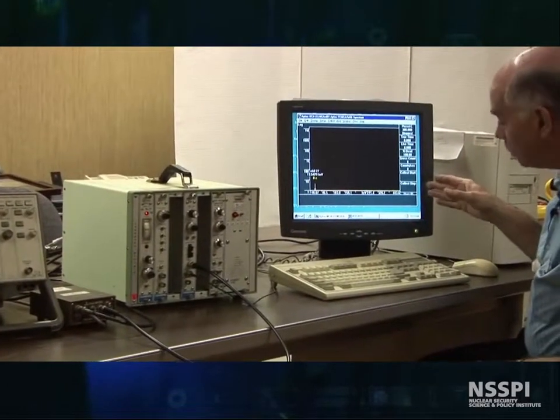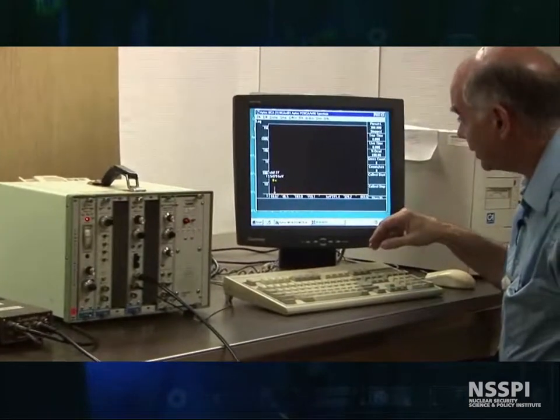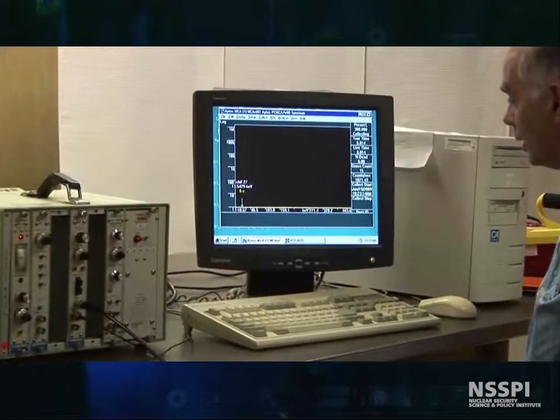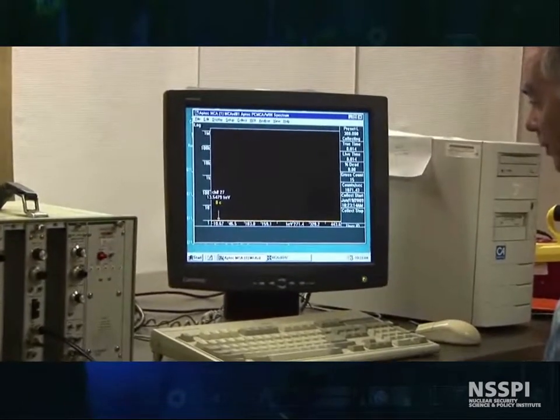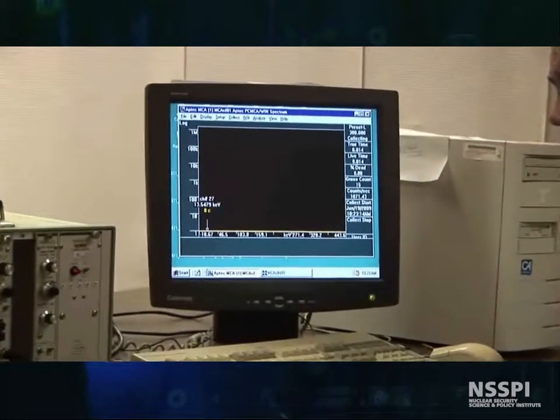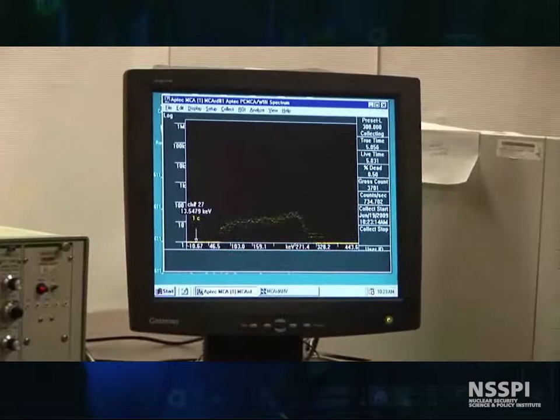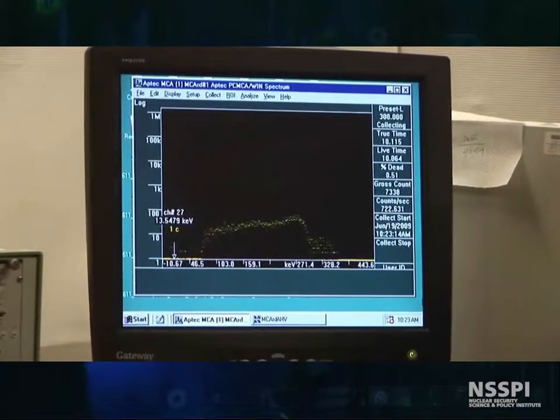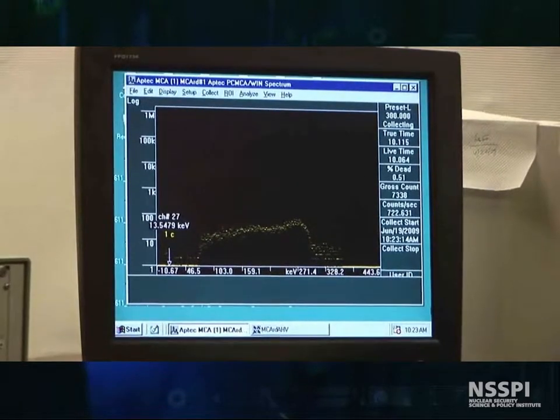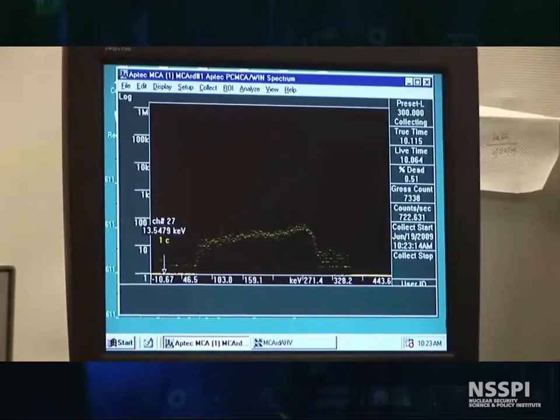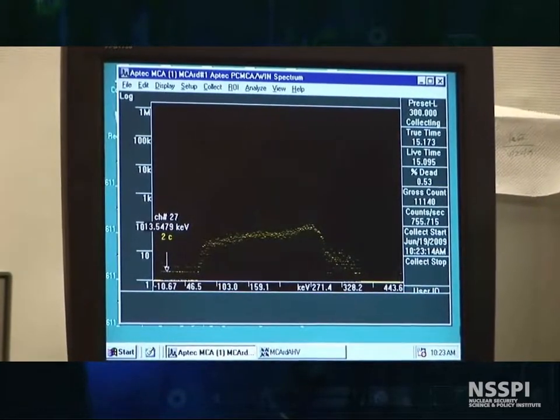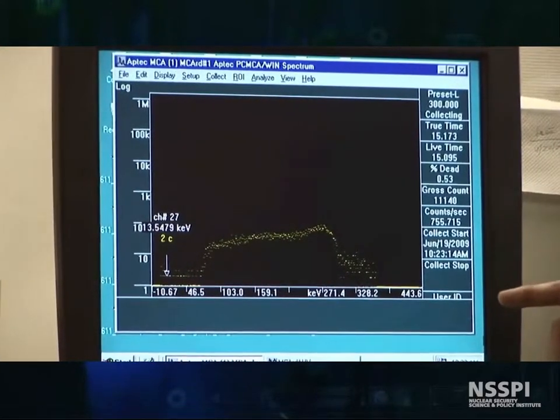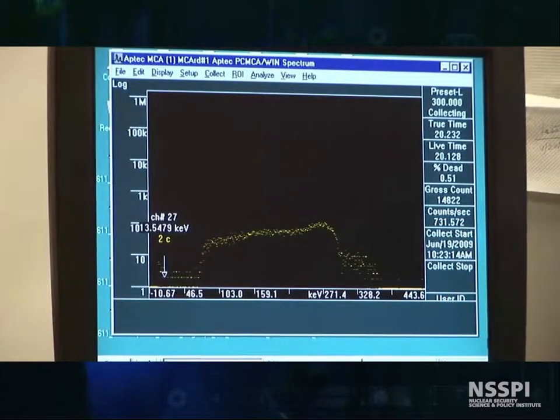Here we are — this is where we're going to build our pulse height distribution. I can start it. It scans for about a second, and then it'll begin to display. Here it comes, and this looks pretty good. We're going to just let the MCA run for a minute and build in the spectrum. The reason we tortured you with statistics earlier is you know that these are Poisson distributed in each channel.